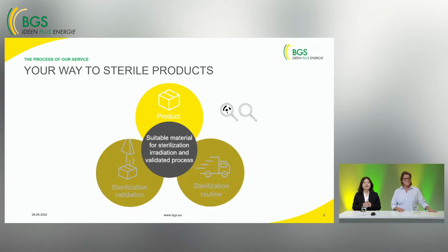Irradiation helps you to obtain sterile products, which according to EN 556, terminally sterilized medical devices can be designated as sterile if the theoretical probability of there being a viable microorganism in the product is equal to or less than 10 to minus 6. This means that one viable microorganism is allowed in 1 million products. You need to process your products under defined conditions. For example, the microbiological load after the production may not exceed a certain level.